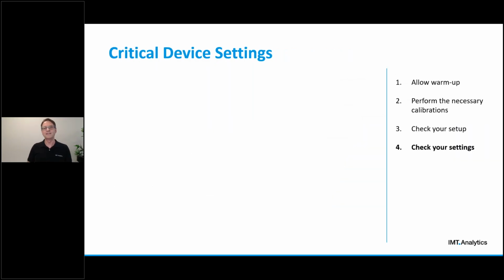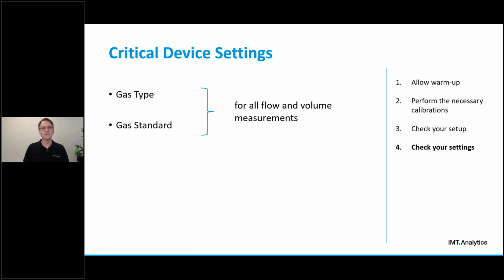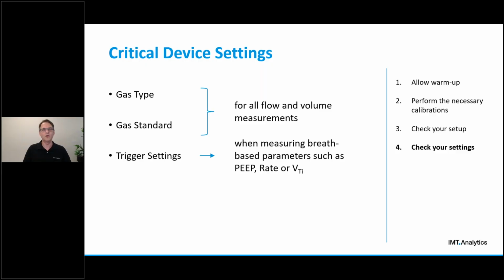The most important settings on your gas flow analyzer are gas type and gas standard. These two settings are crucial for all flow and volume measurements. The third one we're going to discuss is trigger settings. Trigger settings are relevant when we want to measure the so-called breath-based parameters, such as PEEP pressure, respiratory rate, or for example, tidal volume. And last but not least, it's the measurement parameters themselves that we can configure on our gas flow analyzer. Gas flow analyzers can measure many different parameters, so we must ensure that we look at the right measurement and have it set up with the correct unit of measure.